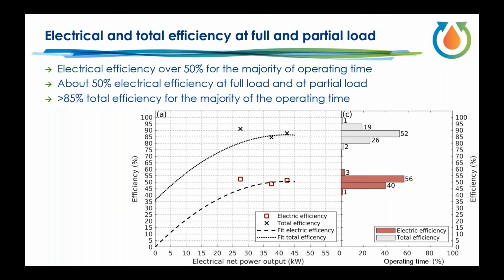What is also significant here is the shape of these graphs. The dashed lines represent all operating points, and the dots or X's represent the major operating points that the system has been on for a very significant amount, or the majority, of the time. If you look at the shape of these curves, you notice that high efficiencies are reached not only at 100% load, but also at relatively low partial load. So from roughly 60% to 100% of nominal load, both electrical efficiency and total efficiency stay at these high values, about 50% and about 85% in total.